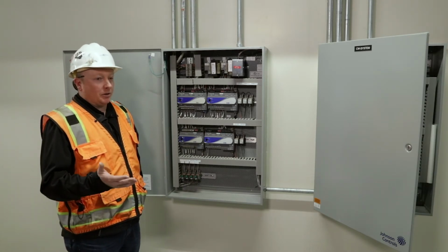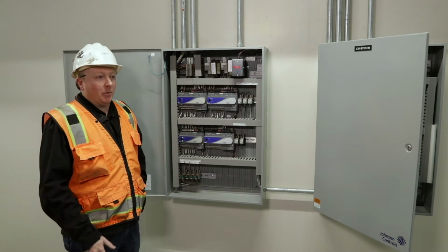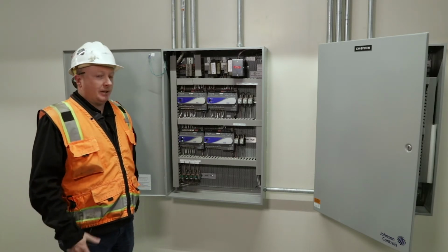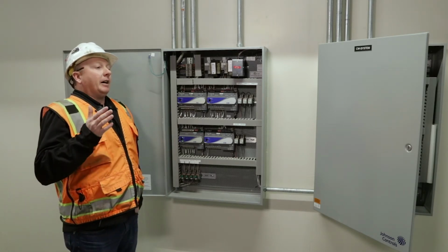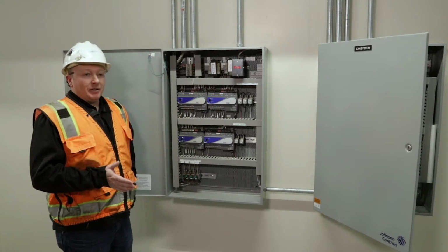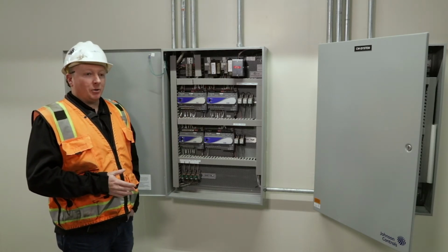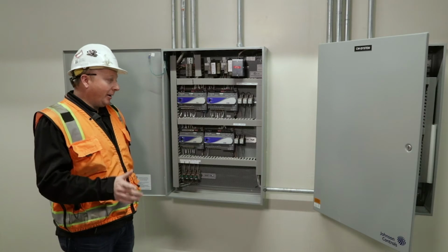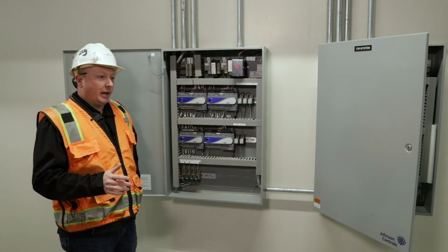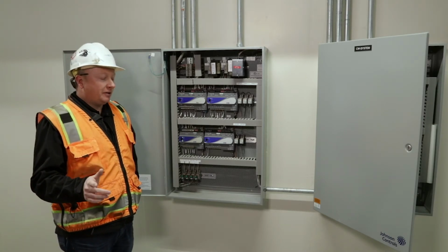And out there, we're controlling for condenser water supply temp. And that's obviously adjustable. The condenser water pumps have VFDs on them. The primary chill water pumps do not. On the primary pumps, there's also no hand-off-autos on the starters.